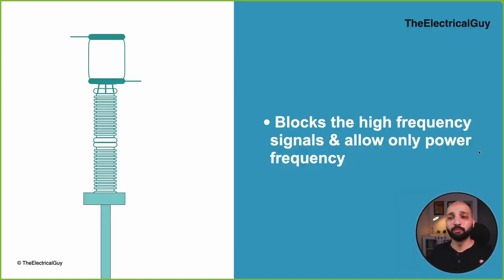And hence I said a few minutes ago when we talked about CVT that it also helps in PLCC communication. That's why CVT is generally preferred, because it can be used for dual application. If CVT is not provided, then generally the substation will have coupling capacitors. Clear? Again, that too is for the purpose of power line communication. So the wave trap is used to block the high frequency signals and allow only power frequency signals.